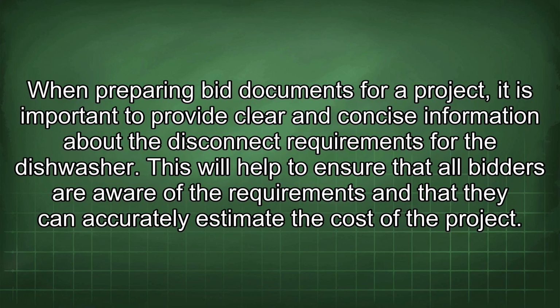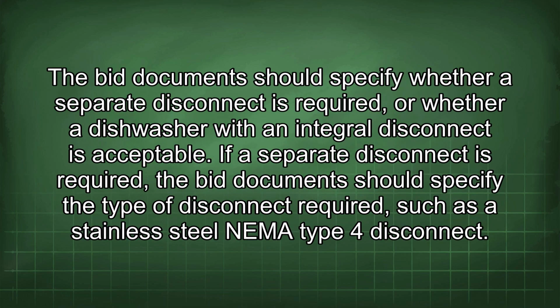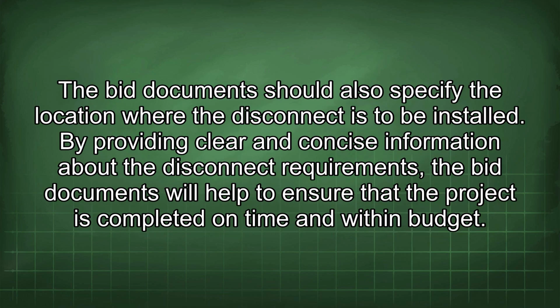When preparing bid documents for a project, it is important to provide clear and concise information about the disconnect requirements for the dishwasher. This will help to ensure that all bidders are aware of the requirements and that they can accurately estimate the cost of the project. The bid document should specify whether a separate disconnect is required or whether a dishwasher with an integral disconnect is acceptable. If a separate disconnect is required, the bid document should specify the type of disconnect required, such as a stainless steel NEMA Type 4 disconnect. The bid document should also specify the location where the disconnect is to be installed.